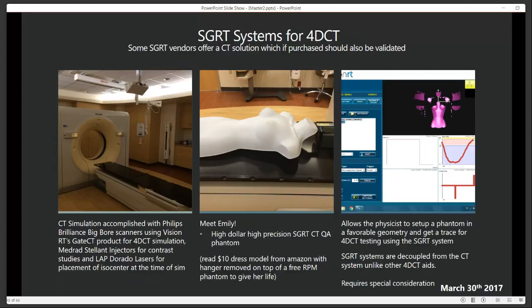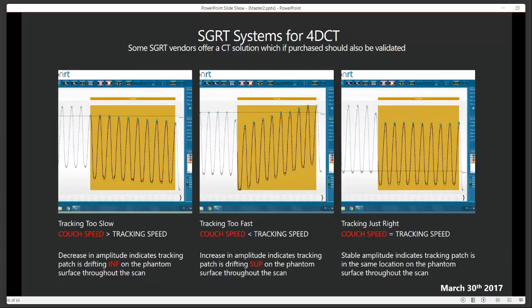If you see the image up in the upper right-hand corner, that's the image because it's a single camera system. You can see portions of the chest of the phantom are not seen because they're shadowed by the breast on the phantom. So you can see that there's some missing information. That's important when putting in the speed of your couch, because if you look at the left, if I tell the system to track at a certain speed and the couch is moving faster than the tracking speed, you'll see a drop in amplitude.